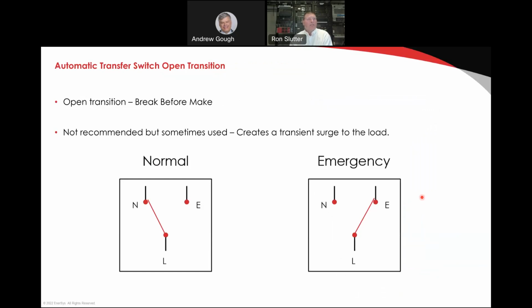So this is a simple transition, break before make, which means when we go from normal to emergency, there is a distinctive interruption in the power between the two sources. Okay, that interruption can produce unwanted transient issues to the load. Now obviously when we move from normal to emergency under the situation that we've lost normal, that's a dead transfer, right? So this source becomes dead. The generator starts up, comes online, and when this source becomes available, we transfer to the emergency source.